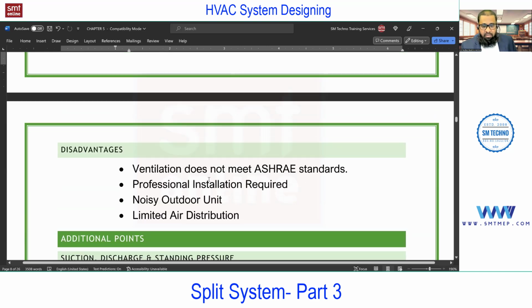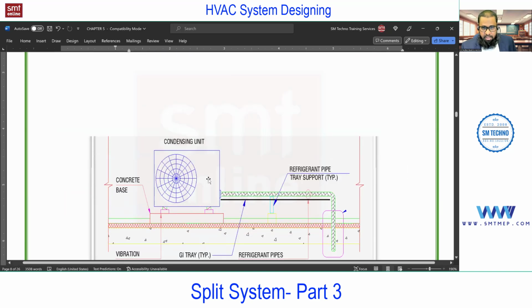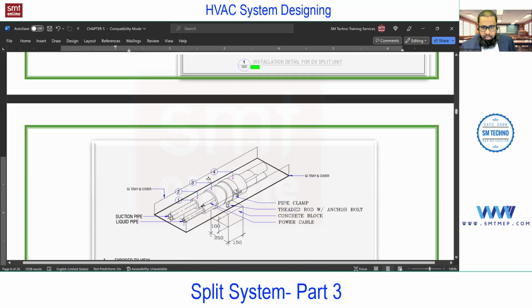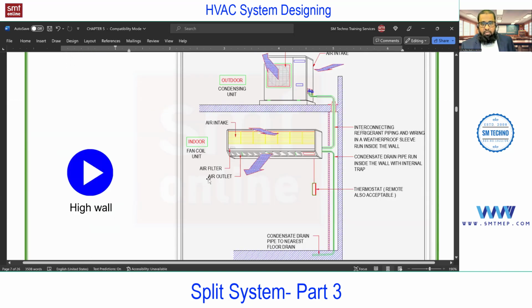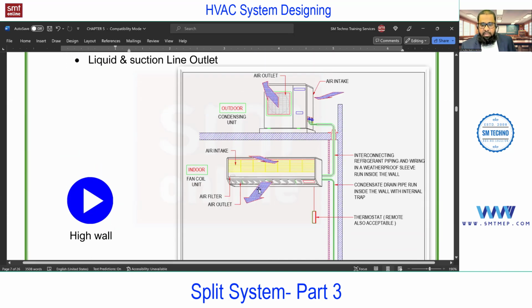You see, the major disadvantage in this is that ventilation is not as per ASHRAE or not as per standard. We are following ASHRAE in this training program. So we use this ASHRAE standard. But if you are concerned with using Kuwait standard or any other standard, we don't have a ventilation option in this, no? Because it is circulation of the room air only. There is no addition of what? You see, the same air circulates. There is no option for adding fresh air. So this is the one major disadvantage in this.